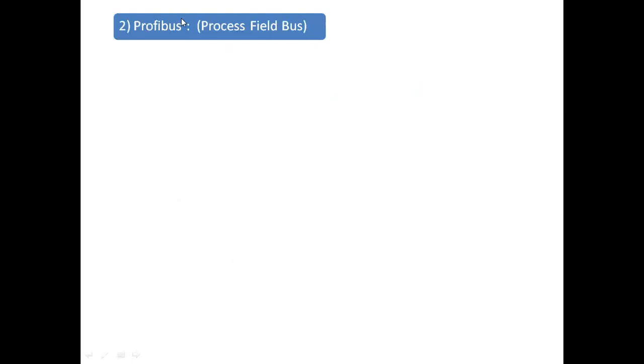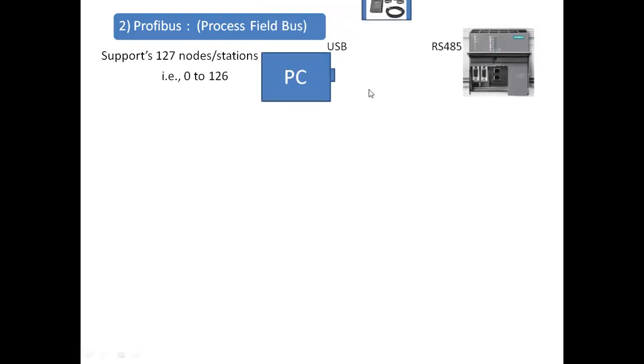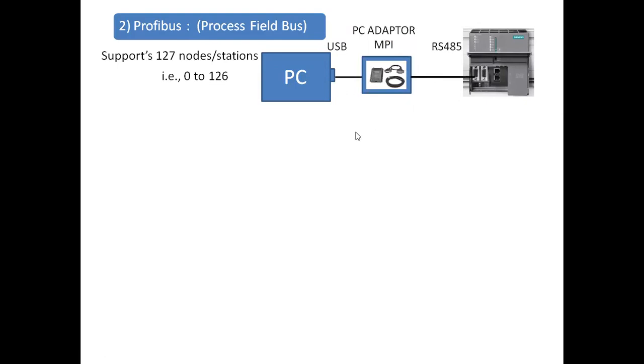Next we come to Profibus — one of the main and mostly used protocols in the field. Profibus stands for Process Field Bus: 'fi' means field, 'b' means bus, and bus means traveling — your data is traveling. It supports up to 127 nodes or stations, starting from 0 to 126. For example, from PC to PLC we use a PC adapter MPI for communication.